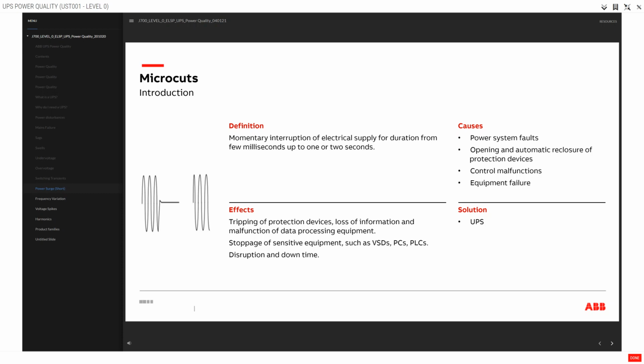Microcuts. Definition: momentary interruption of electrical supply for duration from few milliseconds up to 1 or 2 seconds. Causes: power system faults, opening and automatic reclosure of protection devices, control malfunctions, equipment failure. Effects: tripping of protection devices, loss of information and malfunction of data processing equipment. Stoppage of sensitive equipment, such as VSDs, PCs, PLCs. Disruption and downtime. Solution: UPS.